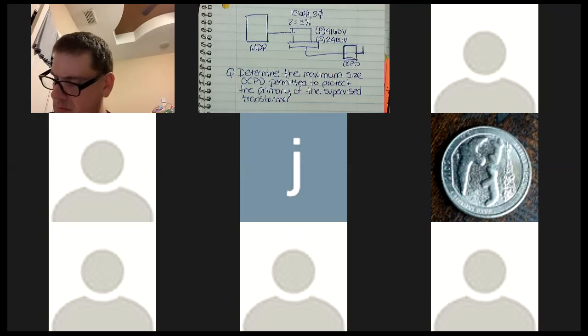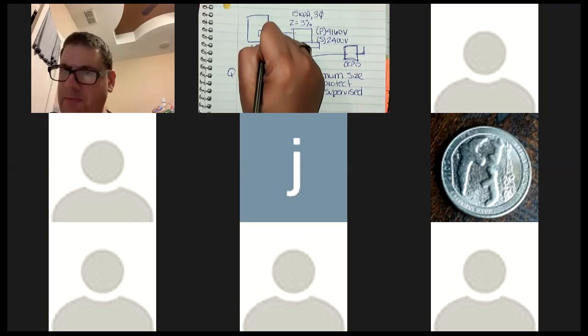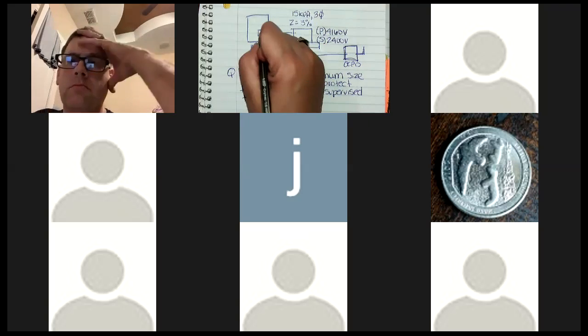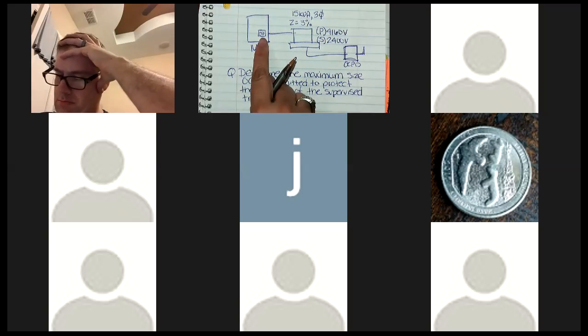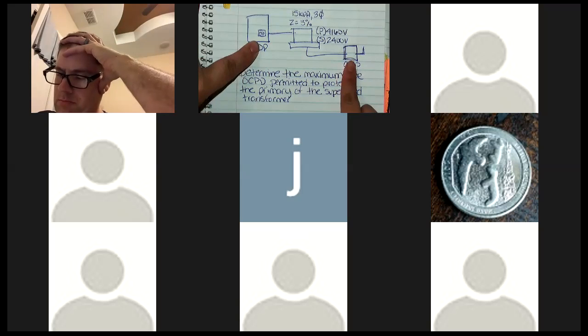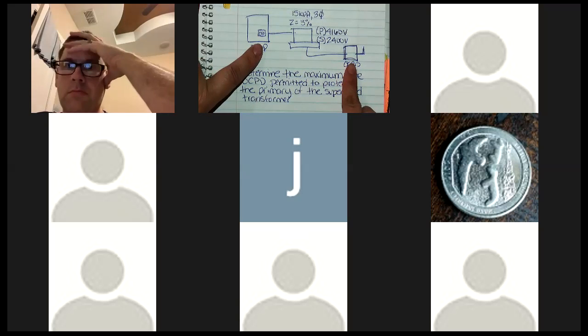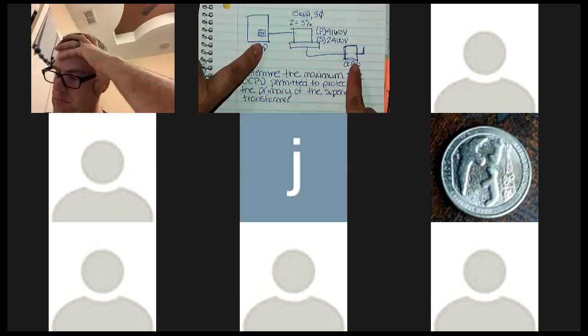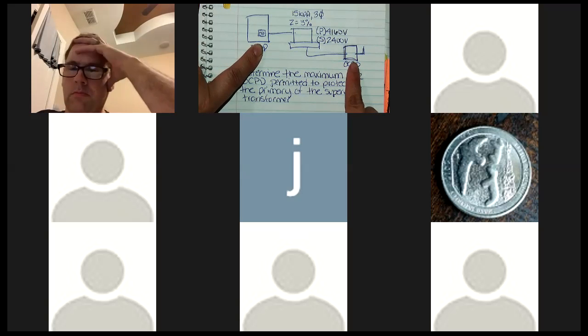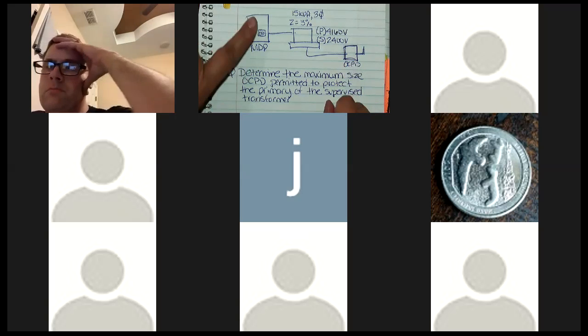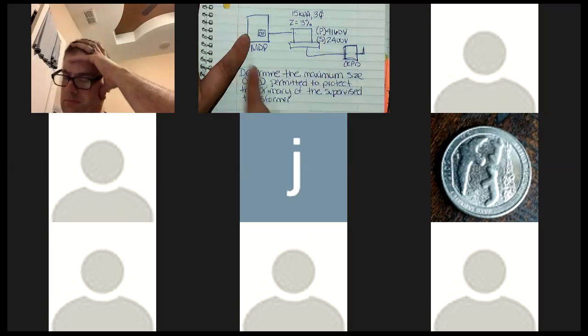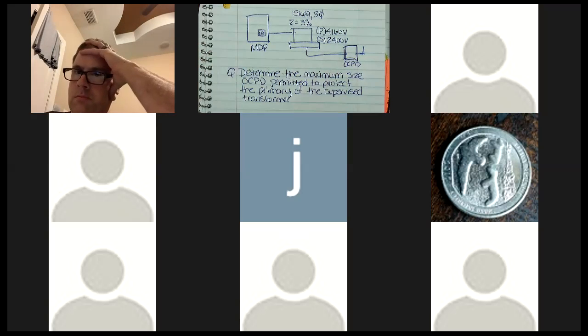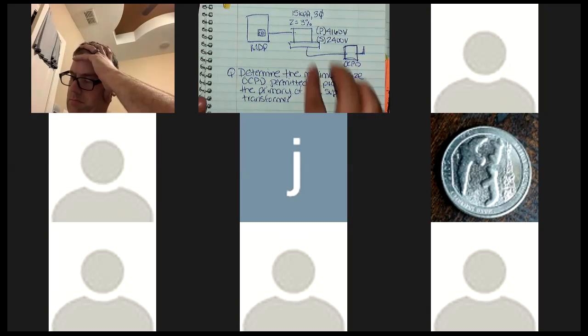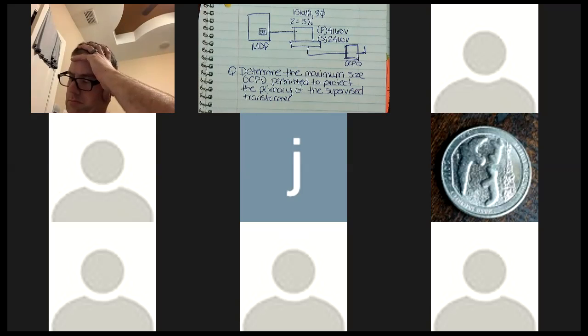Does everybody understand why? You're looking for, it's asking you, what is my CB right here? That's all it wants to know. But you have two overcurrent protection devices. You have one on the MDP that it's asking you for, and then you can see that it has a disconnect with fuses over here. While it's not asking you for the size of fuses, you still need to get the circuit breaker on this side and size it as if you were going to do both, okay? Because at some point along the line, you're still going to need to figure out that overcurrent protection device on the fuse, on the disconnect.